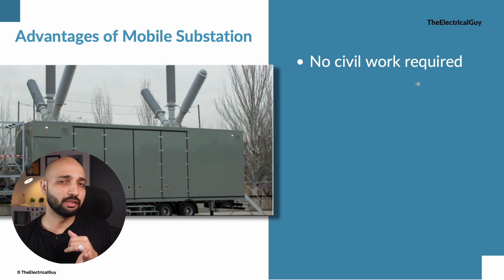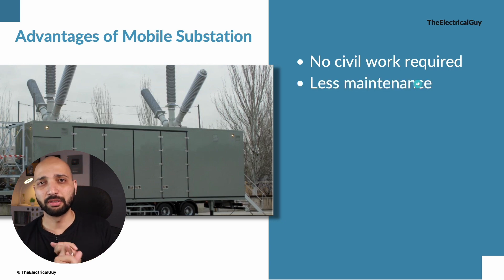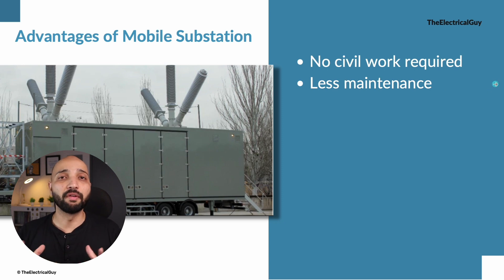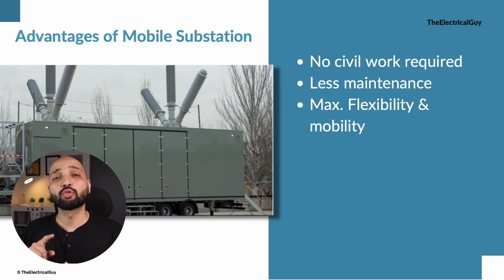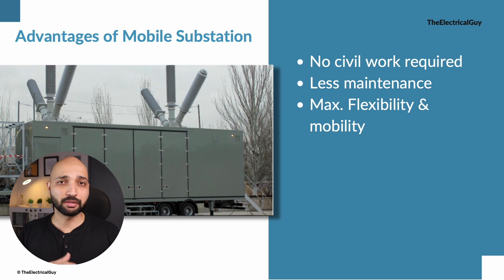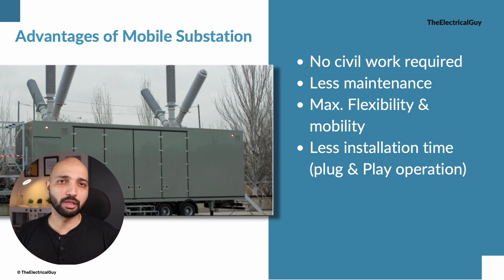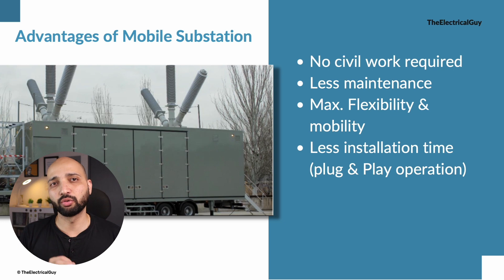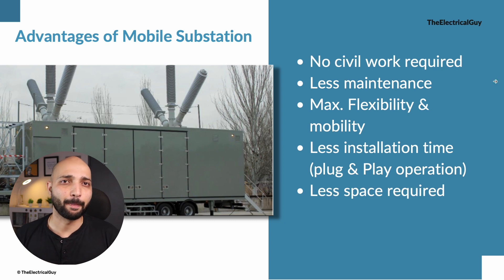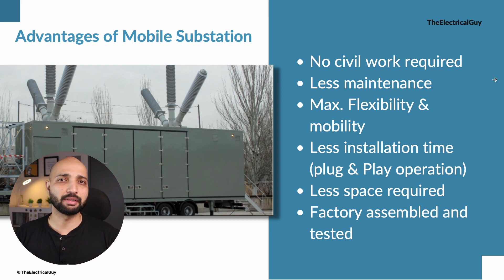Using a mobile substation offers many advantages over building a new substation. There is no civil work required, it reduces maintenance cost since it is enclosed in a container, and it offers maximum mobility and flexibility. I can take this trailer to another site where maintenance is needed and bypass that substation. It does not take much time to install and commission, it is completely factory assembled and tested, and the space requirement is very minimal.